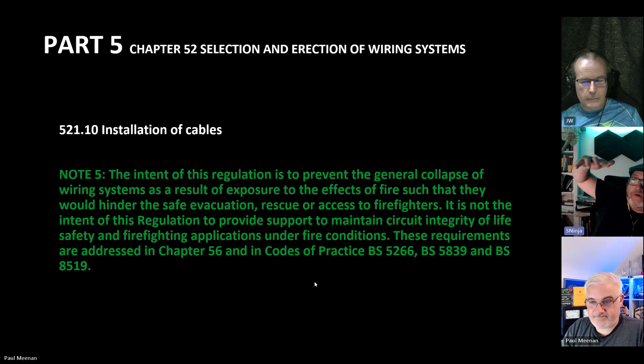The question which got raised, and the IET covered this quite neatly in their webinar, was people would take the whole premature collapse, integrity of the cabling, to mean does the cabling need to continue operation? That's what drove this question. The IET very succinctly said, look, this additional note is about - we're not talking about circuit integrity. Circuit integrity is covered under BS 8519, 5266, and 5839. So that's emergency lighting, fire alarms, and life safety systems, or other systems deemed essential. How you do that - I think some places are immature, some places are very good at it. This is just about a nest of disconnected, powered-down junk falling down and entangling firefighters. That's all this is.